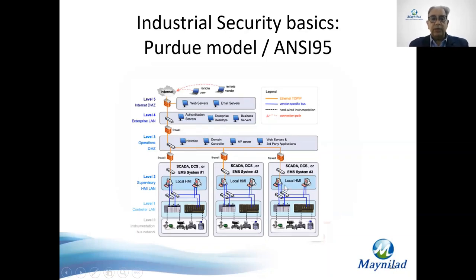Between your OT down here and your IT, you should actually have an industrial demilitarized zone. That means you can't get from IT down here to the OT. Normally what you need is data coming from the industrial side to go up - that's a unidirectional path that you allow. Nothing should go down. Above this is the regular IT network.